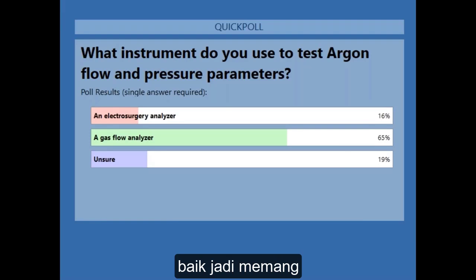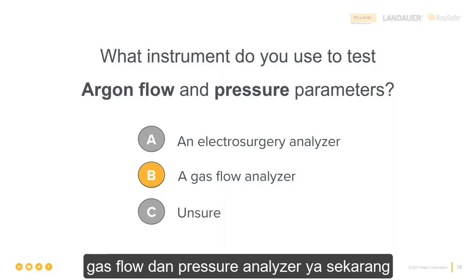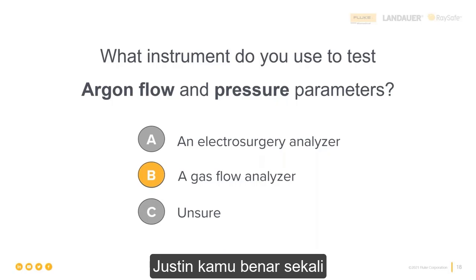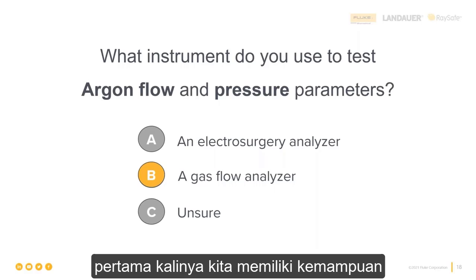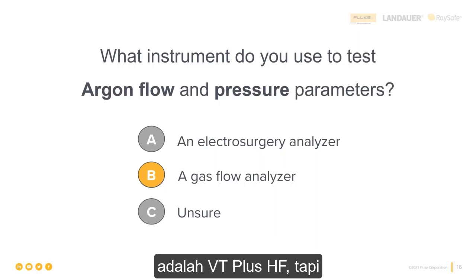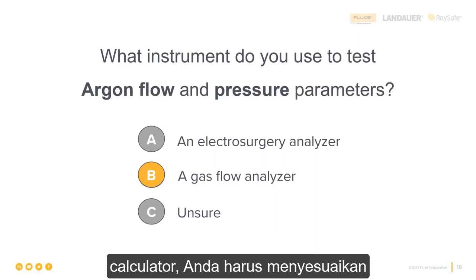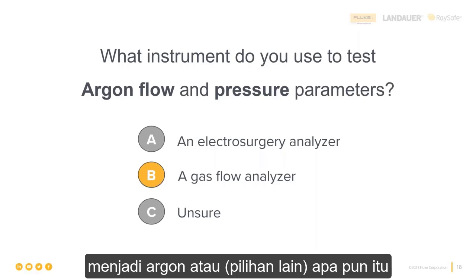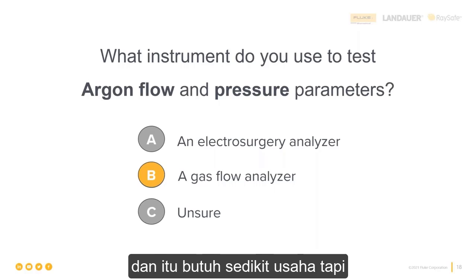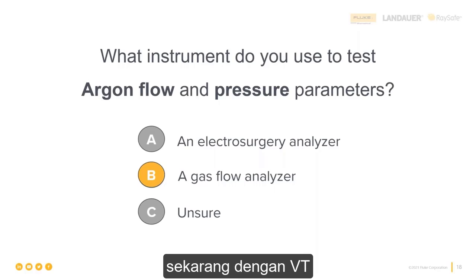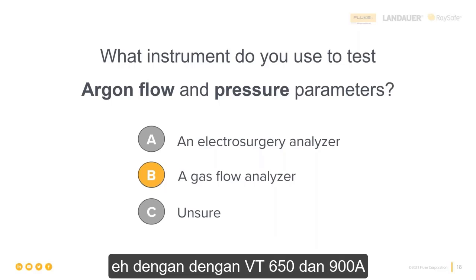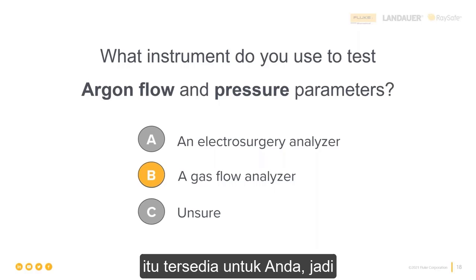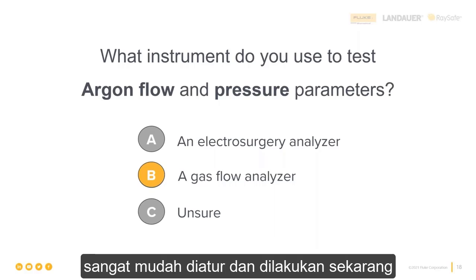Well, so indeed, the answer that we're looking for here is a gas flow and pressure analyzer. Justin, you're exactly right. The first time that we had any ability to provide a test instrument that could help us with this was the VT Plus HF, but you had to customize the user selection for gas type in the gas calculator to argon or whatever other inert gas it was, and that took a little bit of doing. But now with the VT 650 and 900A, it's available to you. So no big problems, right? Push of a button. Super easy to set up and do now.